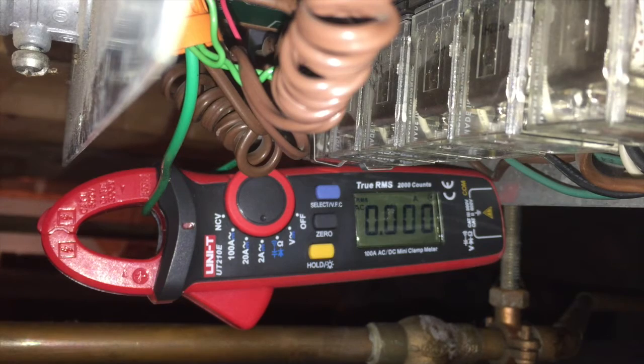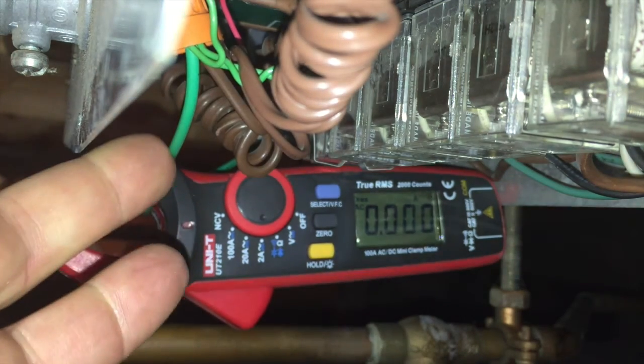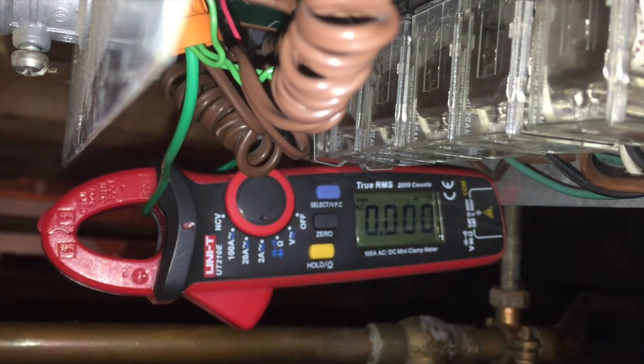Okay, so I've got my clamp meter on the common wire. All three of the commons from the thermostats are joined together to this one common that ties down to the transformer common. So I've got the power off, got the clamp meter zeroed out. It's on the 2-amp range. So let's turn things on and see what kind of power draw there is, or current there is.